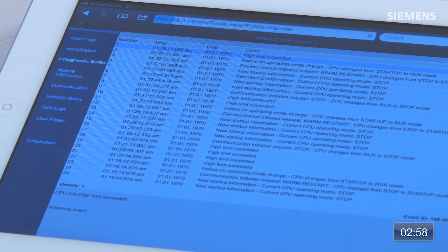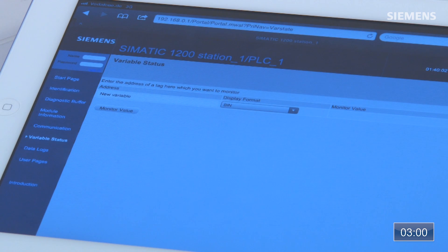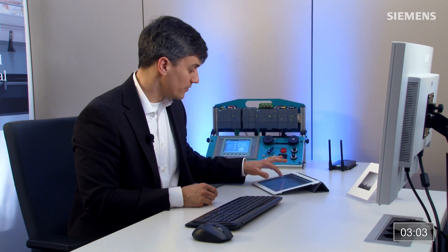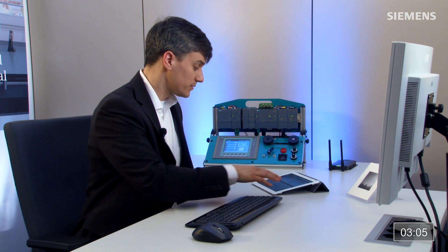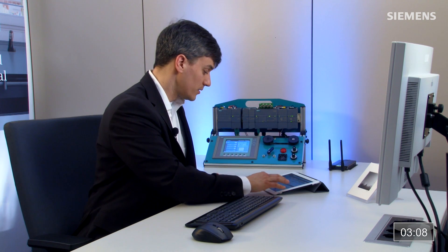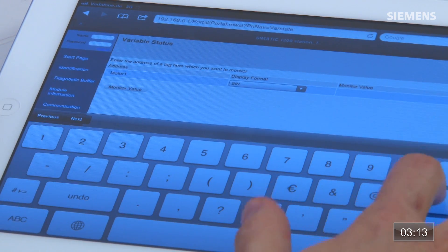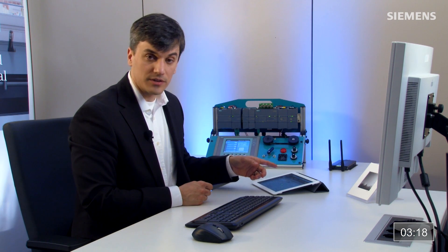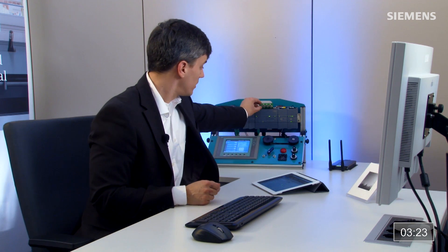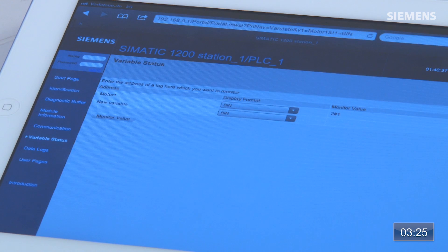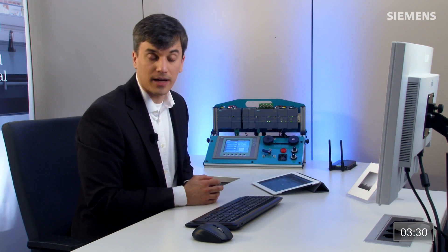Next we can go to the variable status page. As long as I know the tag within the control system, I can monitor any variable I want. Let me clear this and type in one of the variables I know for this program — click go. I can see the status of this particular bit; in this case it's motor 1, a cylinder circuit in this program. Going over and turning it on, I can see the statuses change. You can monitor any analog, digital bit, or word you want in this web server.